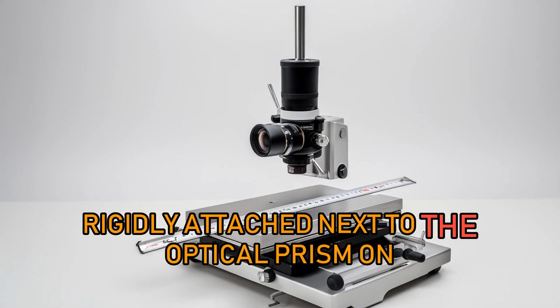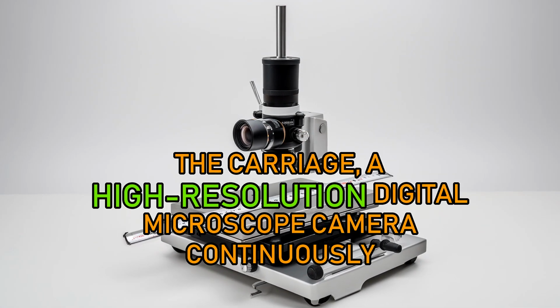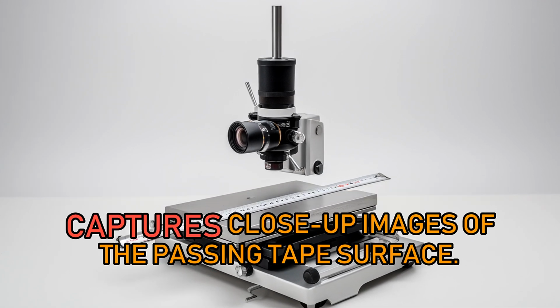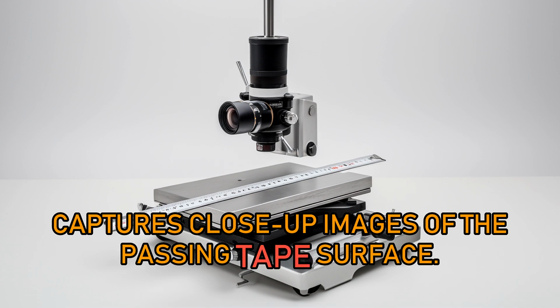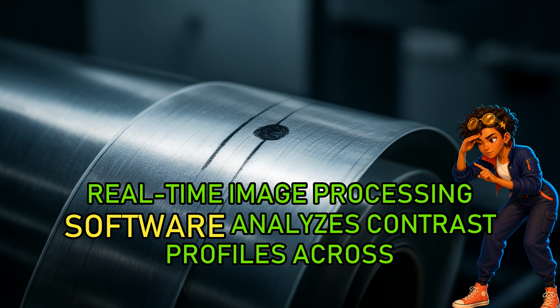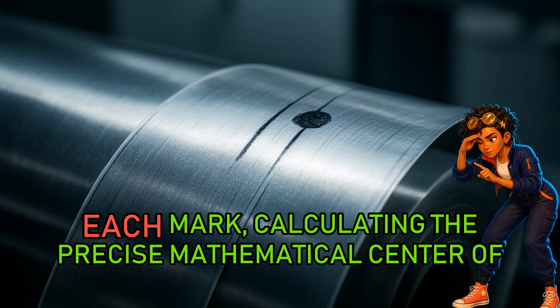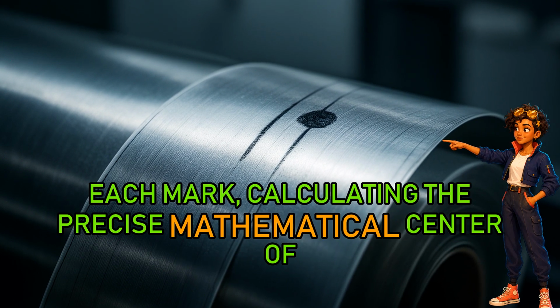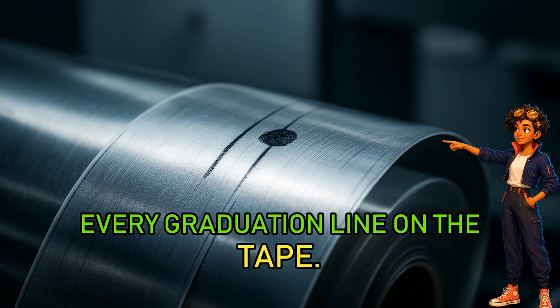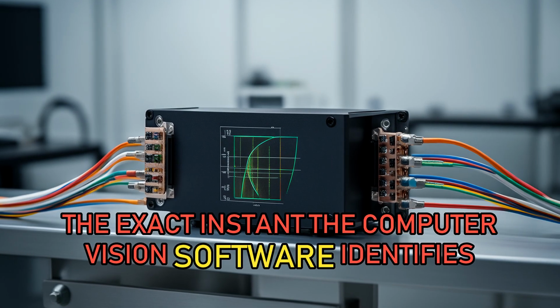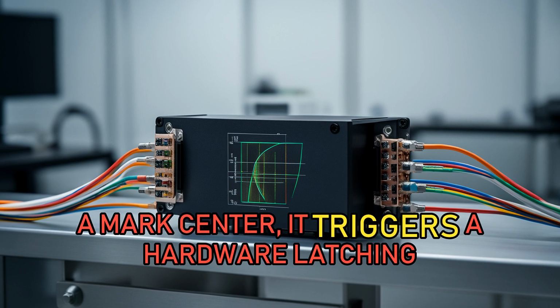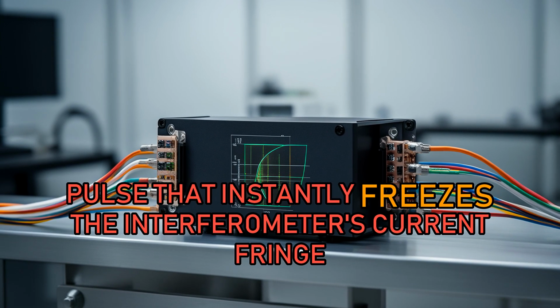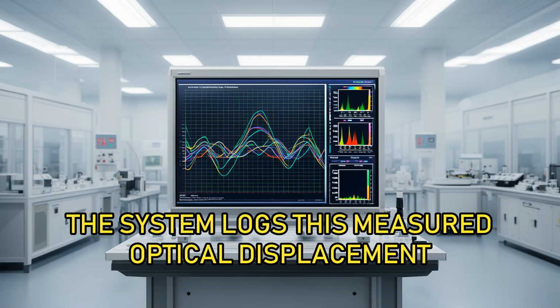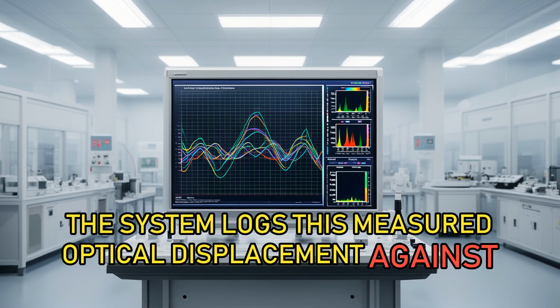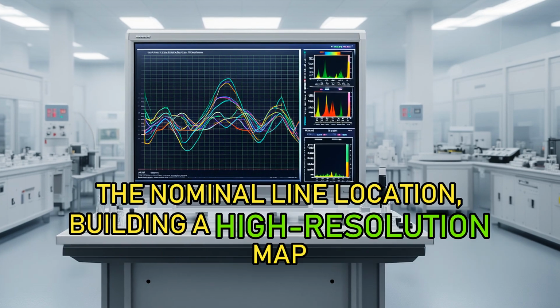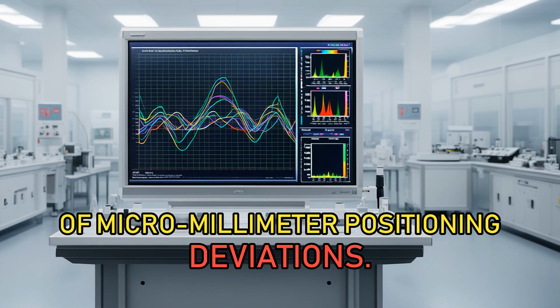Rigidly attached next to the optical prism on the carriage, a high-resolution digital microscope camera continuously captures close-up images of the passing tape surface. Real-time image processing software analyzes contrast profiles across each mark, calculating the precise mathematical center of every graduation line on the tape. The exact instant the computer vision software identifies a mark center, it triggers a hardware latching pulse that instantly freezes the interferometer's current fringe count. The system logs this measured optical displacement against the nominal line location, building a high-resolution map of micromillimeter positioning deviations.